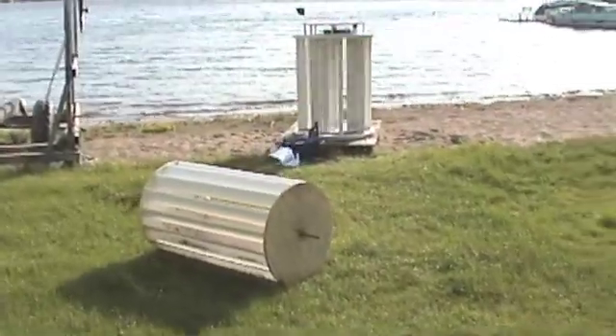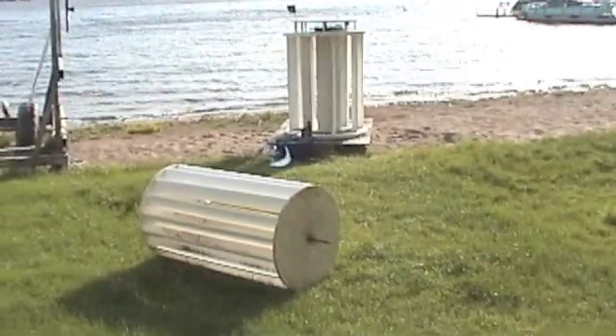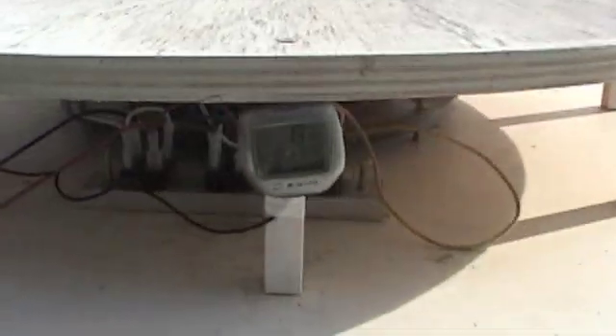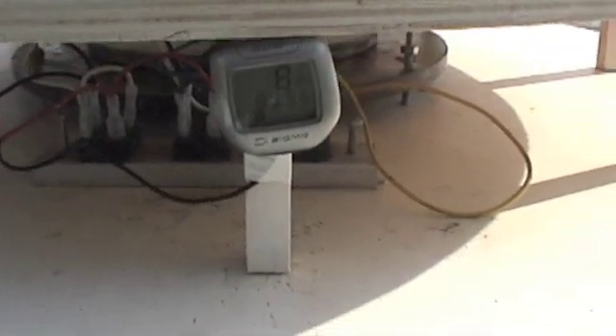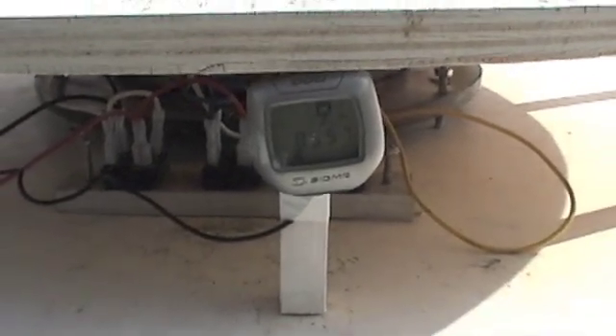I'm taking the other rotor out and putting in a Lenz2 type rotor — we'll see what we got. The RPM reading is times 10, so that's 80 RPM, which is 90.